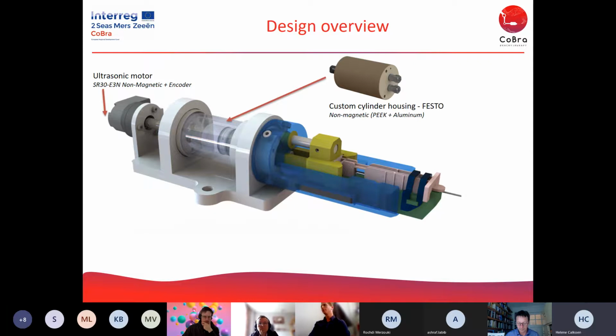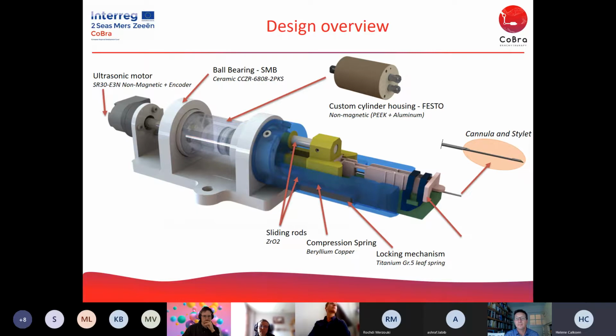The pneumatic cylinder, of course, causes even less distortion. So we developed a custom cylinder together with Festo that would fulfill the requirements that we needed, because the standard pneumatic cylinder is usually magnetic. So we had them update it to remove all magnetic components, so it would be suitable for use in MRI. Also the bearing, we used a ceramic bearing to make it suitable. And then the other parts, we have a spring in the system. Therefore, we selected the material that would be the best option, and that also holds for the other components.